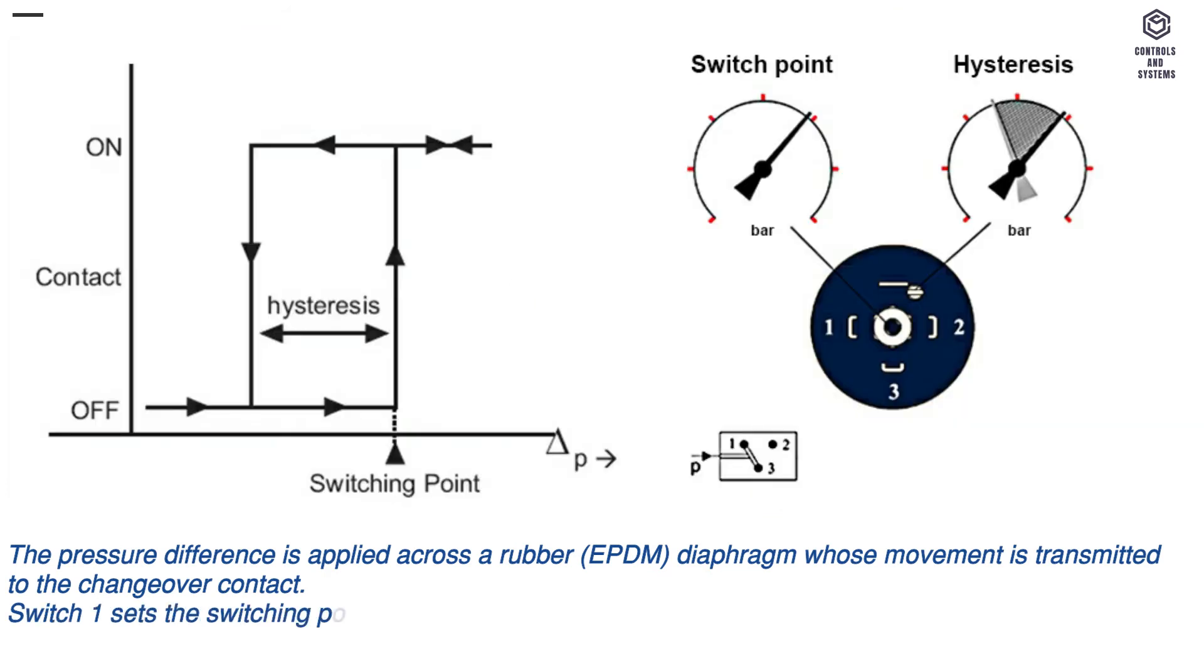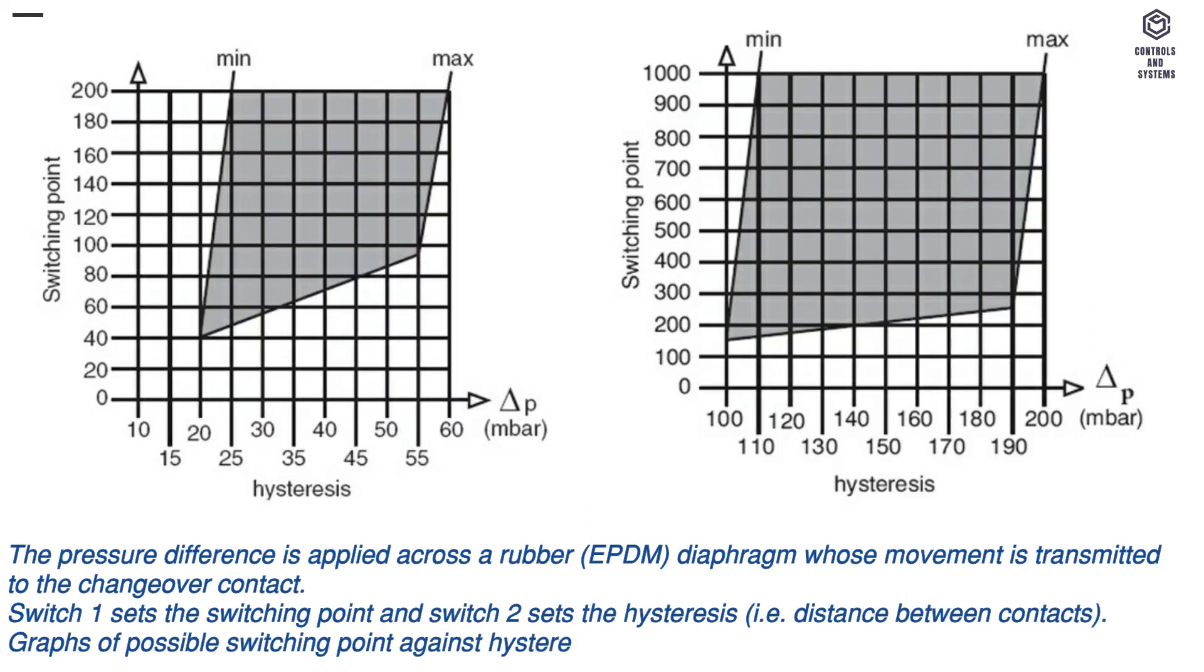Switch 1 sets the switching point and switch 2 sets the hysteresis, that is distance between contacts. Graphs of possible switching points against hysteresis are shown below for both ranges of sensor.